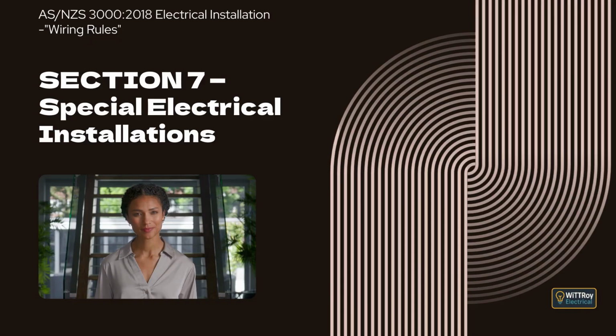Clause 7.2.6.2.2 Segregation of cables for fire detection and alarm systems. This clause explains that conductors for fire detection and alarm systems must not be enclosed with conductors of different safety services or with conductors of any other wiring system. It explains that effective segregation may be achieved by dividing ducts or trunking into separate channels with continuous barriers, by physically separating wiring systems from all others by at least 50 mm or using effective barriers, and by ensuring conductors of different fire and smoke detection and alarm systems are not combined together or mixed with other wiring systems within the same multi-core cable.